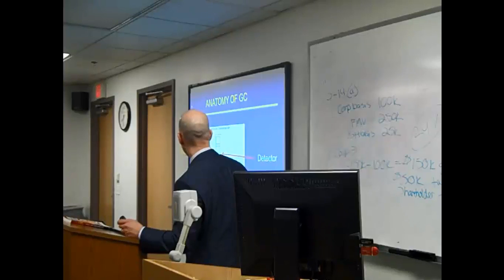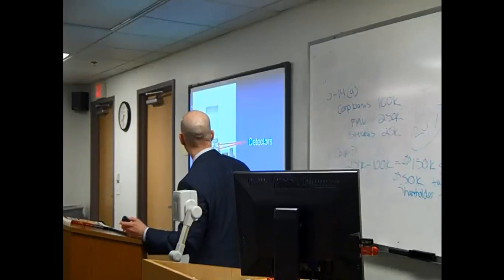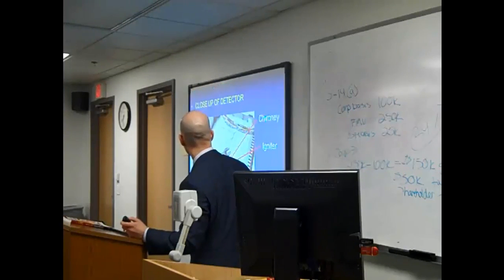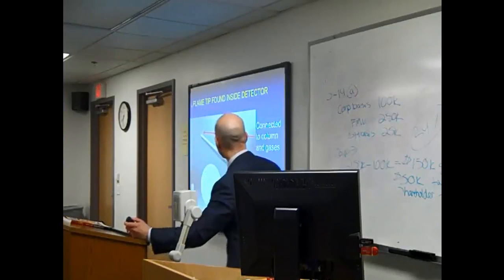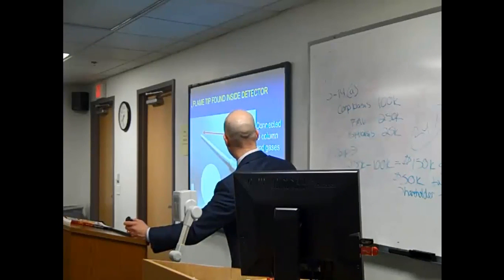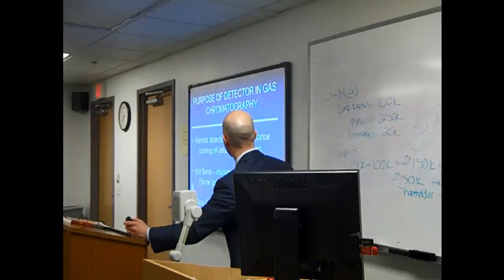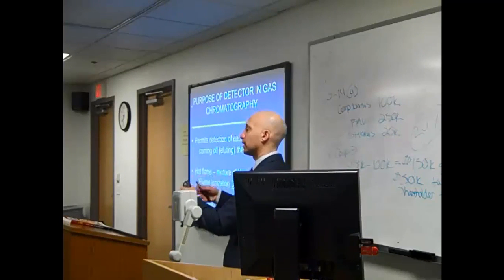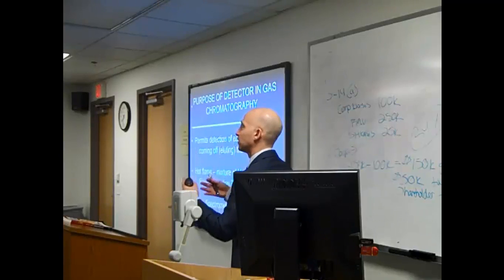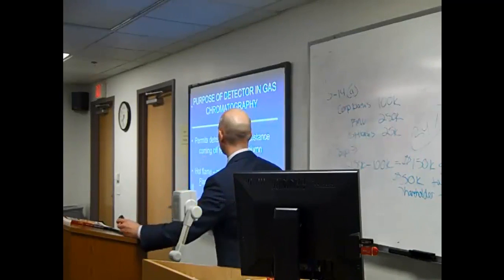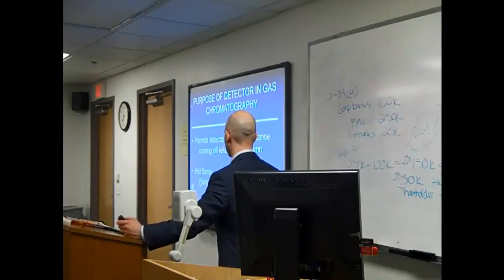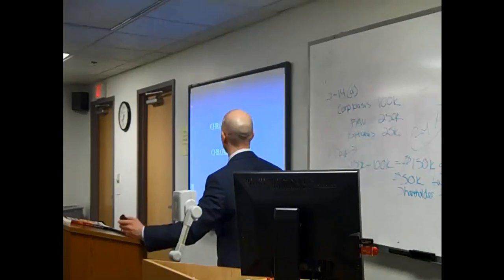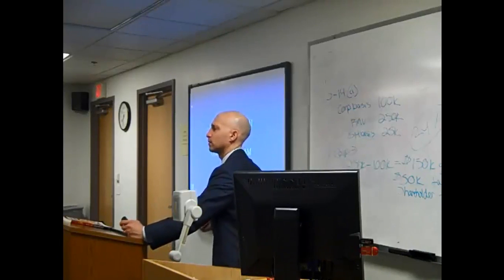All right, so it goes in, goes to the column, and out through the detector. Here are the detectors. There's a close-up view of it. This is the flame ionization. This is the flame tip. You see how small it is. Here's a quarter, which shows you how small it is. And each substance that comes off gets burned up. Again, the amount of the compound, the amount of the molecules that come out, that determines the quantity, all right? And then, with mass spectrometry, there's a different method that's being used.